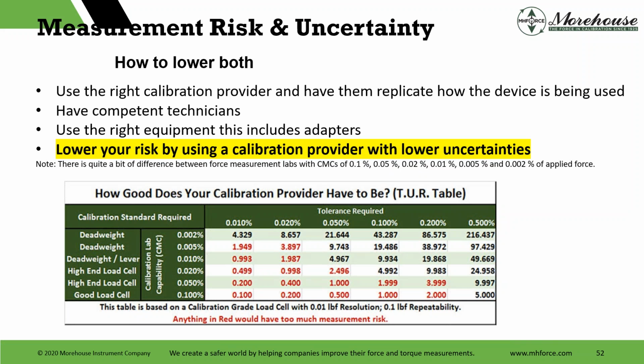And then if you want to lower that measurement risk and uncertainty, the ways to do that are: use the right calibration provider and have them replicate how the device is being used. That's with the right adapters. Have competent technicians. Use the right equipment, which would include those adapters. The hardness of the top blocks makes a difference. Pin size makes a difference. Thread engagement makes a difference. And then the big one that we can offer here is lower your risk by using a calibration provider with low uncertainties. That's the real value proposition here.